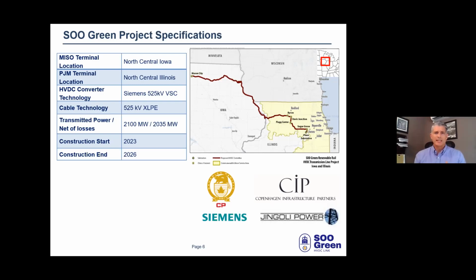To give you an idea of size, each cable has about a 5-inch diameter—about the size of a smartphone or a large wine bottle. We're choosing cross-linked polyethylene because it's a superior insulator; it's also stronger, more impact resistant, and more resilient to adverse environmental conditions. Additionally, these cables are marine grade, meaning they can continue to operate effectively even if exposed to water, which is important near the Mississippi River.